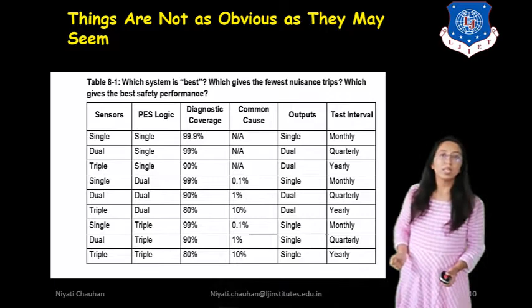First, remember that a safety instrumented system can fail two ways. First, they may suffer a nuisance trip and shut down the plant when nothing is actually wrong. They may also fail to function when actually required. Dual redundant devices can be configured at least two ways. One out of two voting would cause a trip if one sensor were to go into alarm. Here, one out of two. Then 2 out of 2 voting would only trip if both sensors were to go into alarm. So if both sensors go into alarm, then our system will be tripped.